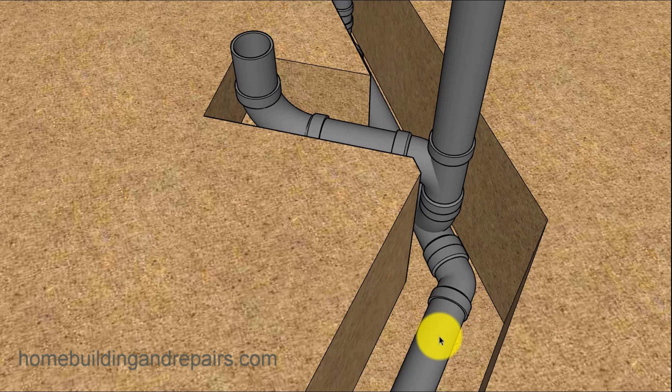But by how much? By just putting a 45 degree pipe in there. But a 90 degree pipe that could actually create some problems. So just something to consider if you're going to make any modifications to this original plan here. So here we have a sanitary tee. This is not the same fitting as the one we had for our horizontal fitting. Once we've come vertical, straight up and down, we can use a sanitary tee here.